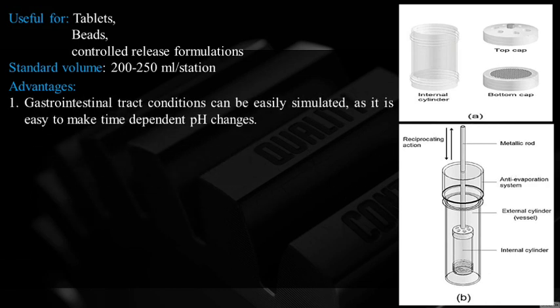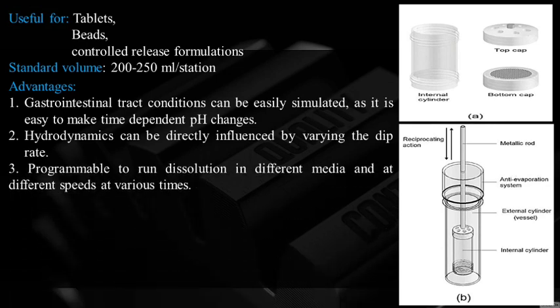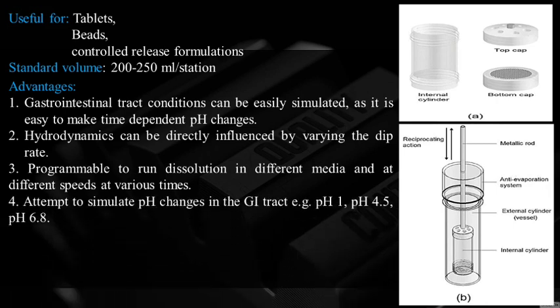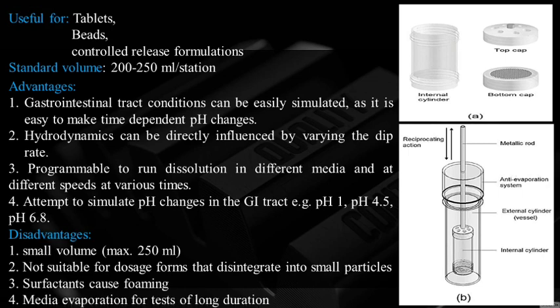The cylinder moves horizontally toward different rows of vessels within specified time intervals. Withdraw the solution from the midzone between the surface of the dissolution medium and the bottom of each vessel. Used for tablets, beads, and controlled-release formulations; standard volume is 200–250 mL per station. Advantages: GI tract conditions can be simulated with different pH in each row, hydrodynamics can be varied by changing dip rate, programmable to run in different media at different speeds. Disadvantages: small volume (max 250 mL), not suitable for dosage forms that disintegrate into small particles, potential for foaming during dipping, media evaporation in long tests.